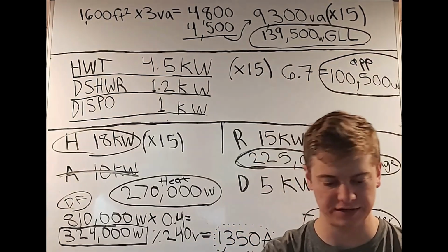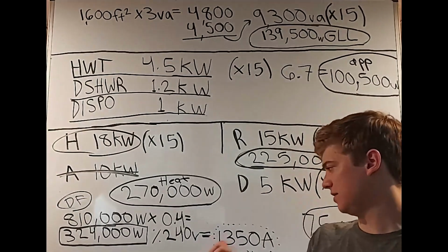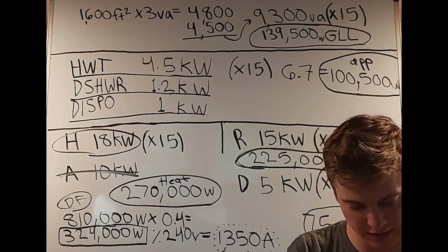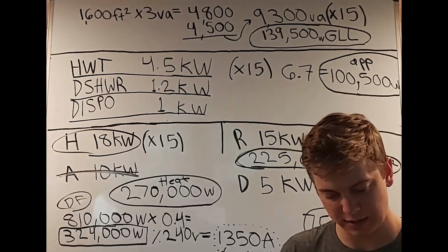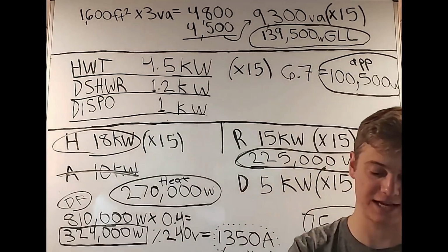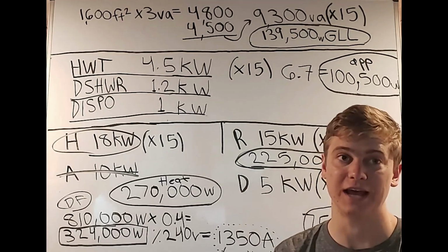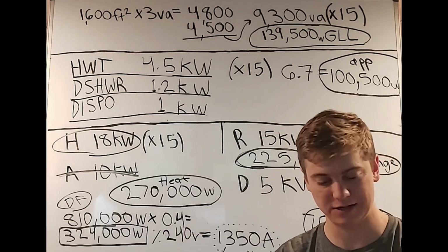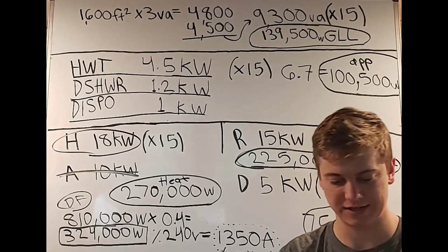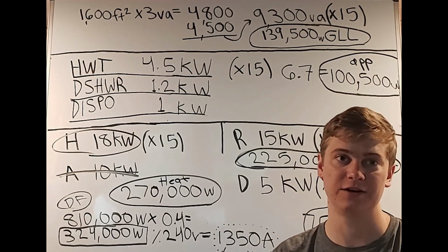To find that out, we're going to table 240.6(A), and we're going to look for that number 1350. We see 1200 and 1600. So that's in the middle of both of those. Now we're used to sizing up to the next size, but in this case we don't want to because it is over 800 amps. Okay, so if we go a page back to article 240.4, section B, it tells us that we can size up to the next breaker as long as it's 800 amps or less.